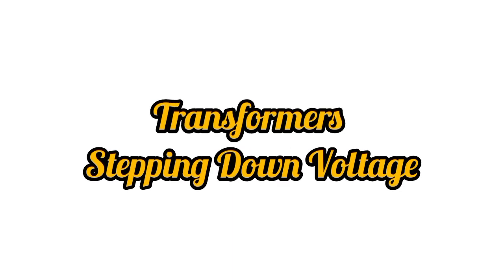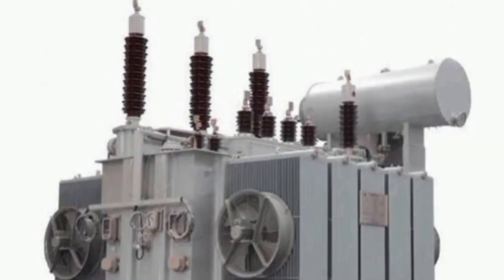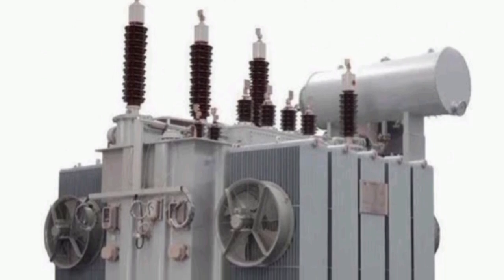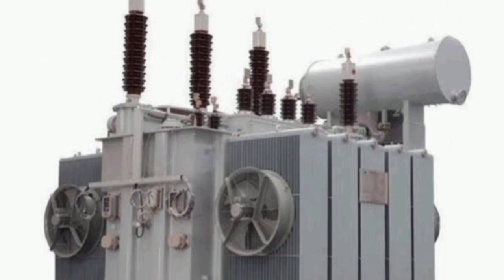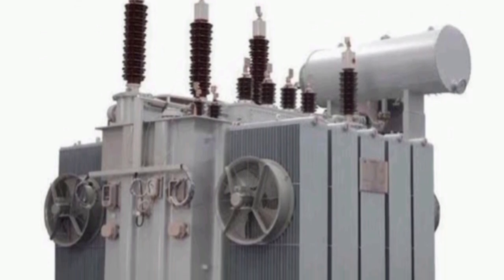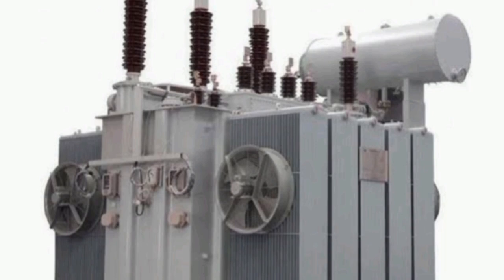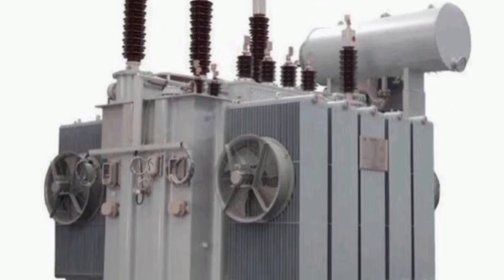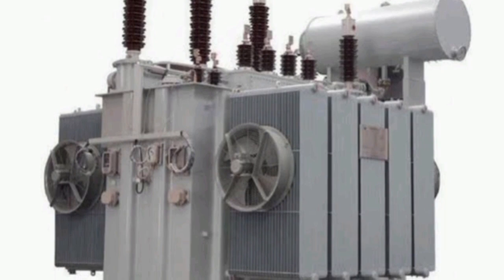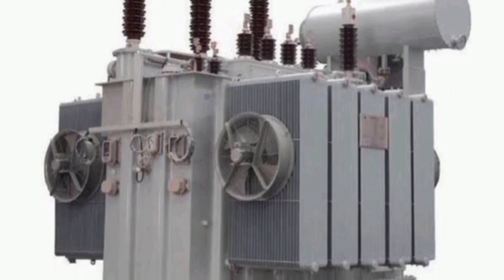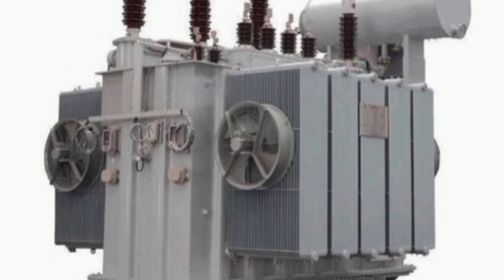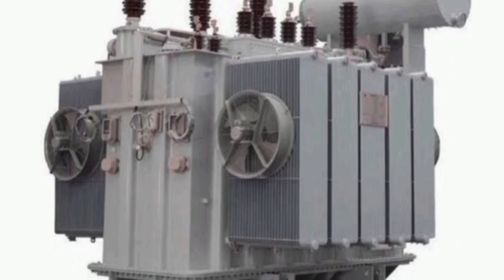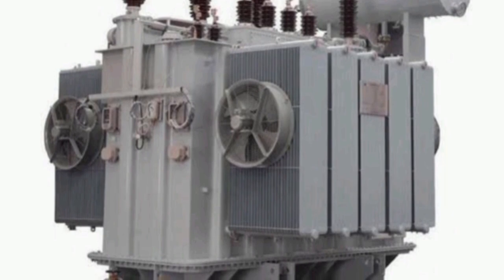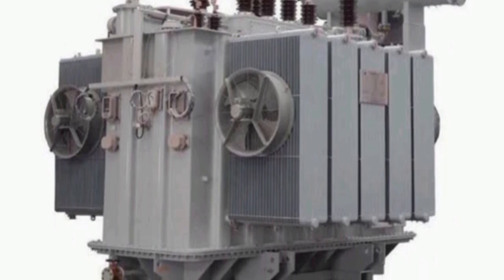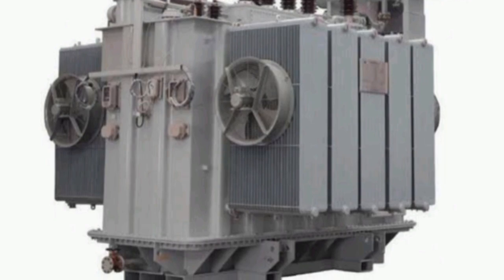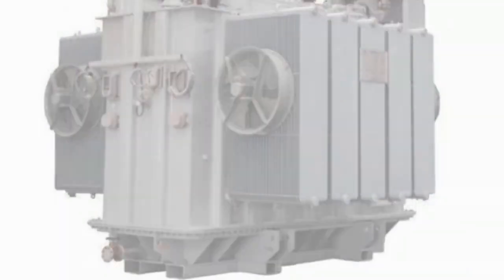Transformers: stepping down voltage. Utility power typically arrives at medium voltage, often between 12 kV and 34.5 kV in the United States. Transformers step this down to low voltage building distribution levels, commonly 480 volt. The transformer performs two critical functions: voltage conversion and electrical isolation. In many facilities, transformers are arranged to support redundancy and load balancing across multiple distribution paths.